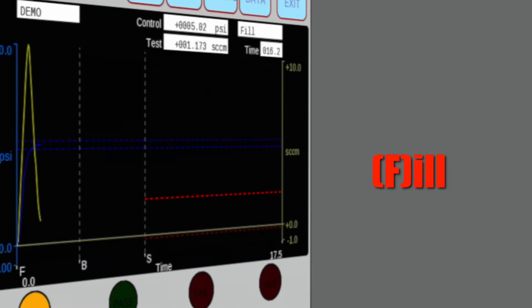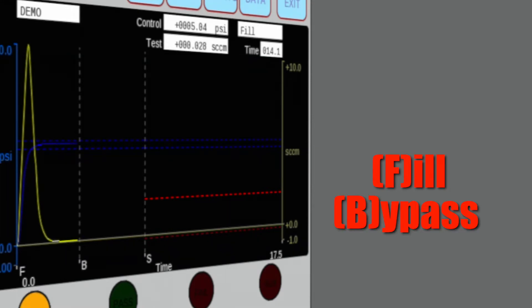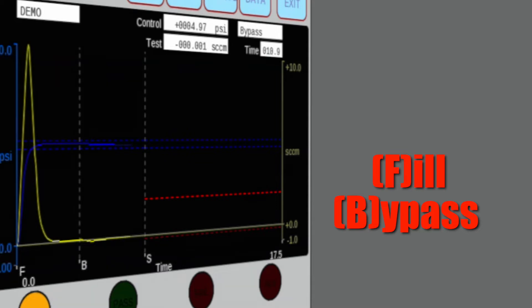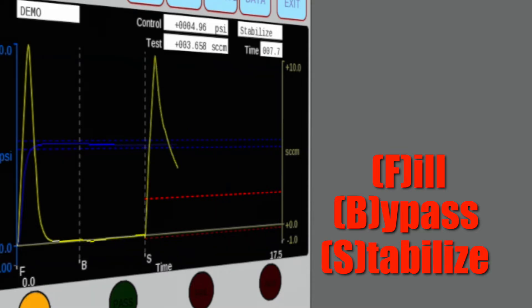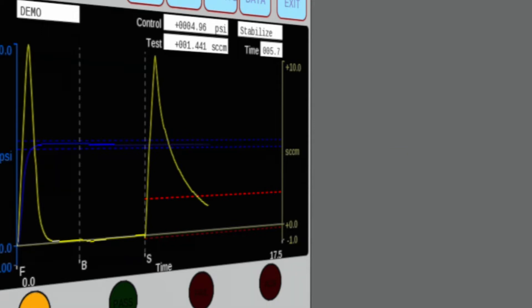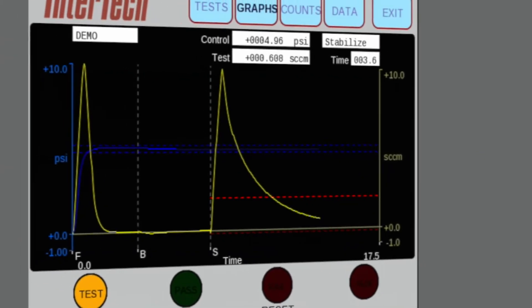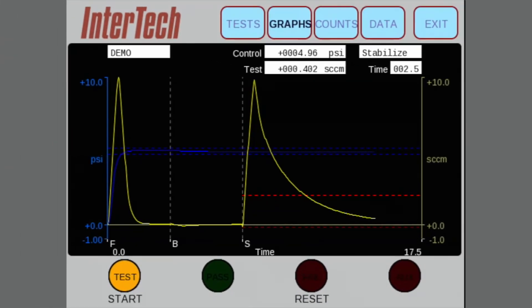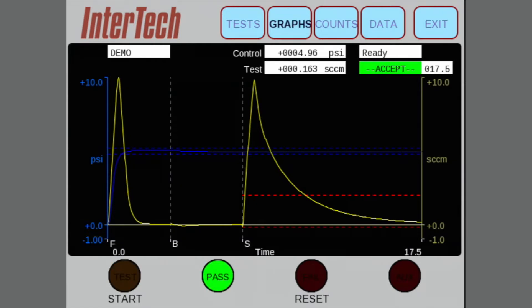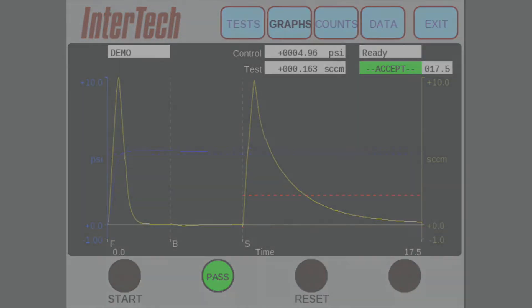In fill mode, the part is filled with air. In bypass mode, the part begins its initial gross stabilization and the sensor is bypassed. Measurement begins in stabilization mode. Once stabilized, the patented mass flow sensor takes an instantaneous real-time measurement of the leak rate flow. The test time required to obtain a leak rate calculation using a pressure decay tester is eliminated.